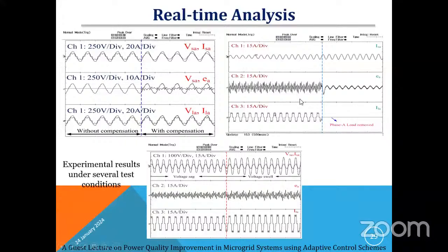And this one is the dynamic condition. The first channel is the source current. Here we have removed a load, the phase A load. When the load is removed, see the variation in the currents and error currents. This is the current in the entire operation, and it maintains good THD content. Here we have also verified voltage sag and swell. Here I have given only two of the four conditions; if you go through my paper, you will get all the information and find all the results for this particular control scheme.